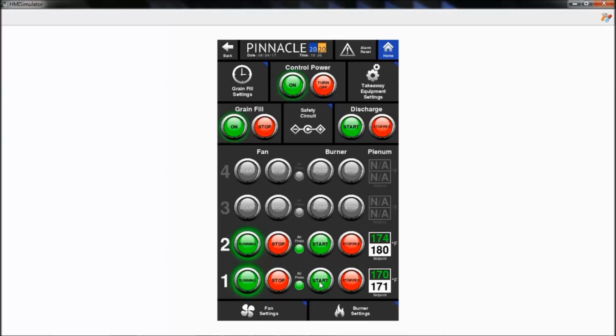When we hit the Start button, the way these ignition boards work, there's a 7-second purge prior to trial for ignition. In order to make sure that the user knows what's going on, when we click Start, you'll see that it says Purging, and it flashes. This is to indicate to the user that you shouldn't expect to see a flame yet, but that there is a process going on in the background.